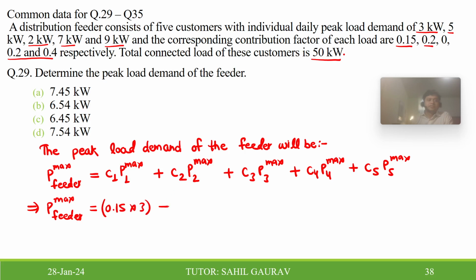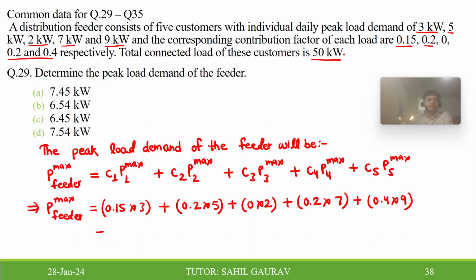0.15 into 3, C2 into P2 max is 0.2 into 5 kilowatt, and C3 is 0, P3 max is 2 kilowatt, C4 is 0.2, P4 max is 7 kilowatt, C5 is 0.4, P5 max is 9 kilowatt. So put all these values: 0.45 plus 1 plus 0 plus 1.4 plus 3.6, you will get 6.45 kilowatt. So B option is correct. Sorry, not B, C option is correct. The options are a little bit confusing.